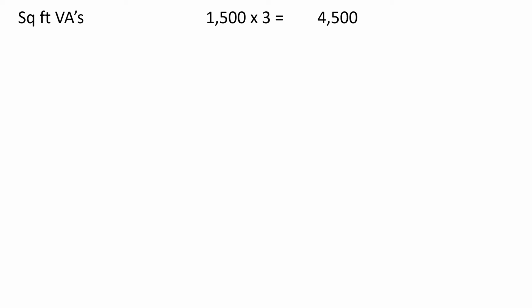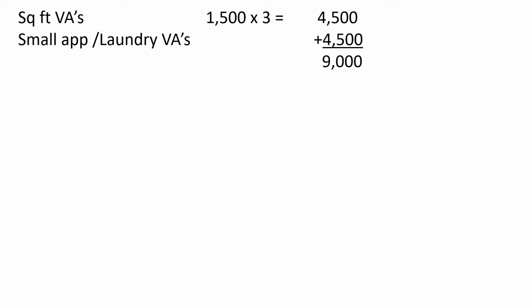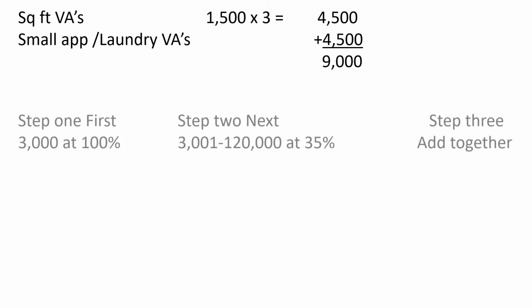So we have 1,500 square feet multiplied by 3 VAs per square foot. That's going to give us 4,500 VAs. Now we have to remember our small appliance and laundry circuits. So that's going to be 2 small appliance and 1 laundry circuit. Each of those is calculated at 1,500. That's going to give us 4,500 VAs for those. Together, that's going to give us 9,000 VAs.